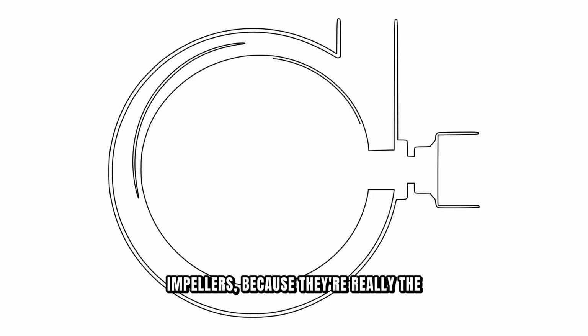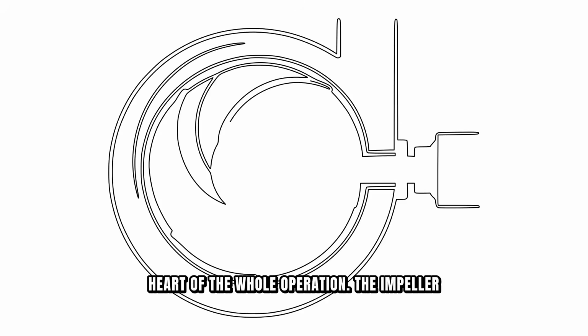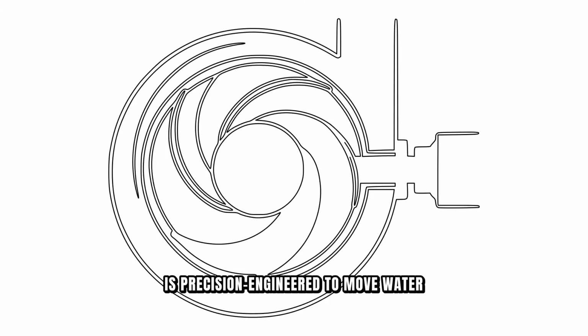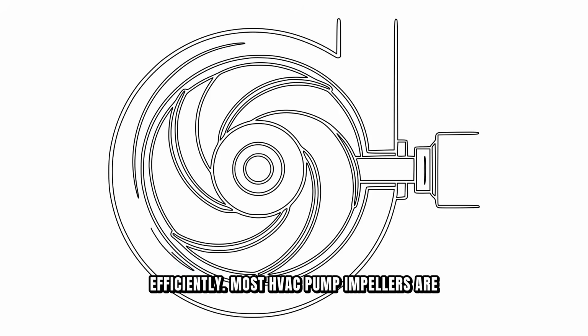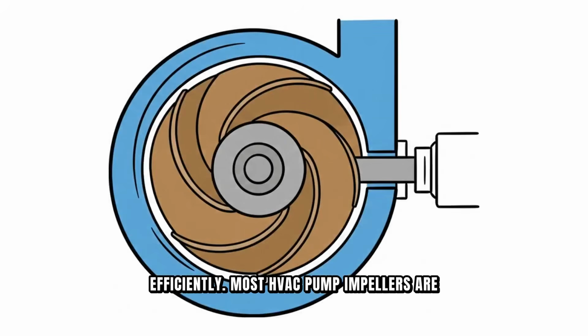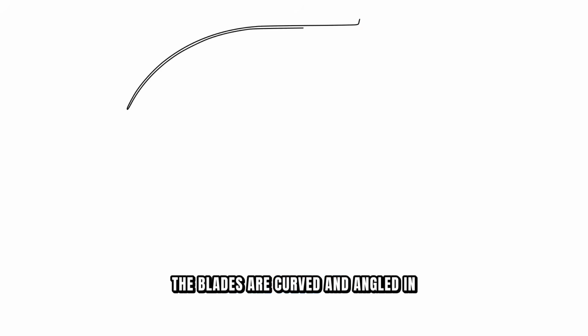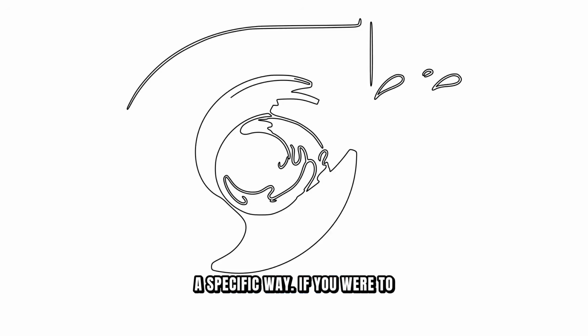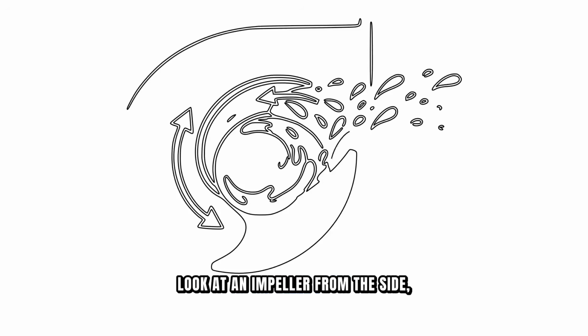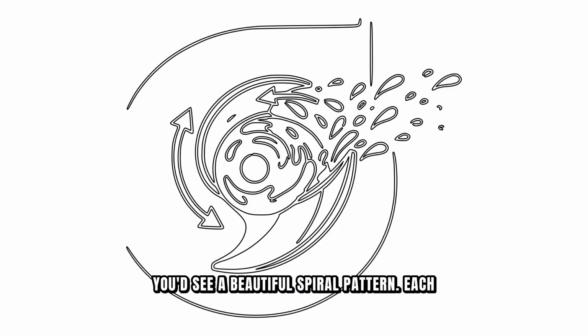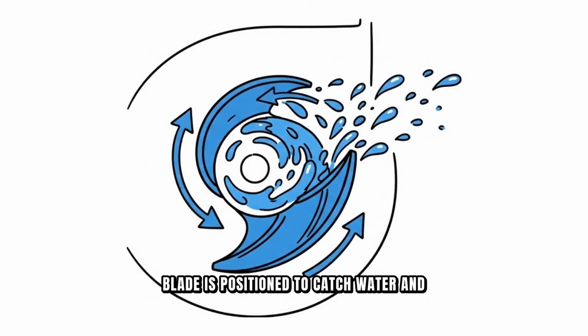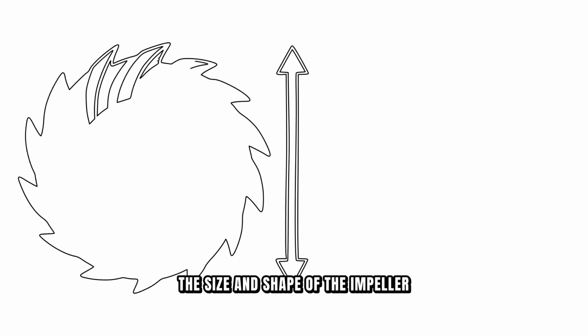Let's talk specifically about pump impellers, because they're really the heart of the whole operation. The impeller is precision engineered to move water efficiently. Most HVAC pump impellers are made of cast iron, bronze, or stainless steel to resist corrosion from water and mineral buildup. The blades are curved and angled in a specific way. If you were to look at an impeller from the side, you'd see a beautiful spiral pattern. Each blade is positioned to catch water and accelerate it outward in a smooth, continuous motion.